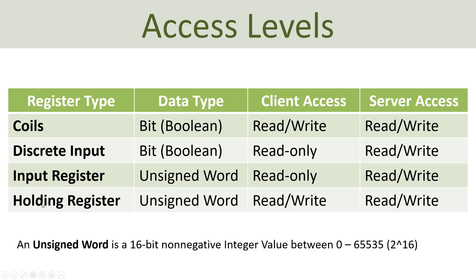The input register and the holding register are unsigned word, so you can use those registers for storing process values, while coils and discrete inputs are only for boolean values. For coils, you can either write data to or read data from them on the client side, while discrete input is read-only, input register is read-only, and a holding register supports both writing and reading.